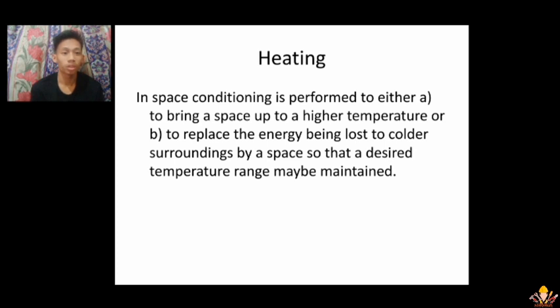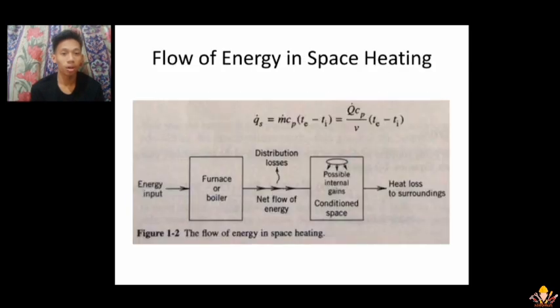Heating in space conditioning is performed either A, to bring a space up to a higher temperature, or B, to replace the energy being lost by a space to colder surroundings so that a desired temperature range may be maintained. We have the figure of the flow of energy in space heating. We have the given equation: the rate of sensible heat transfer equals the mass flow rate times the constant pressure specific heat times the temperature at the exit minus the temperature at the inlet. It also equals the volume flow rate times the constant pressure specific heat over the specific volume times the temperature at the exit minus the temperature at the inlet.